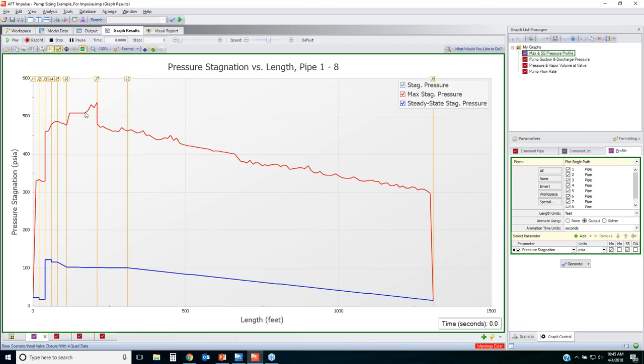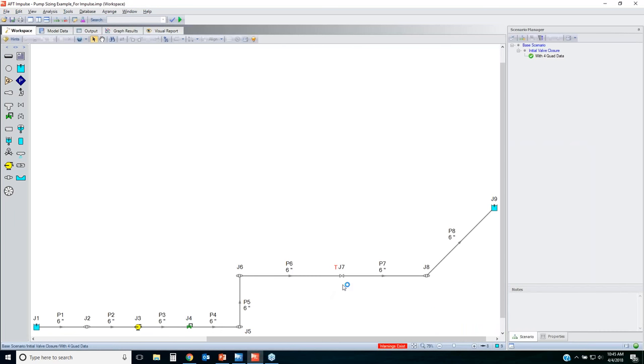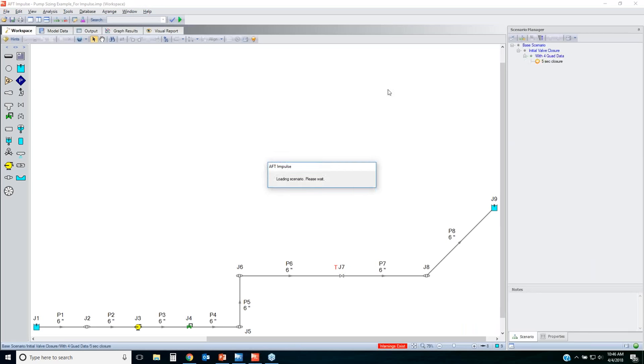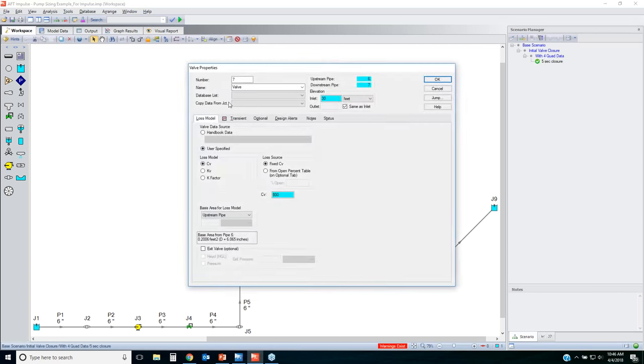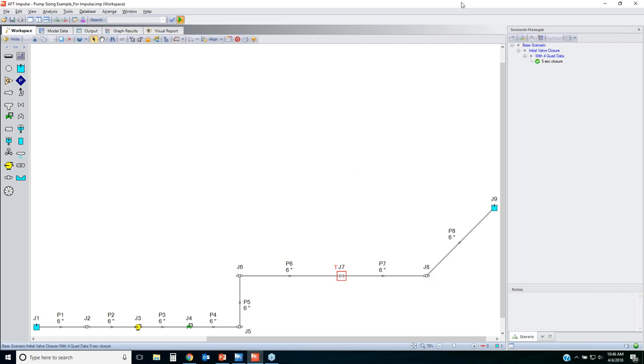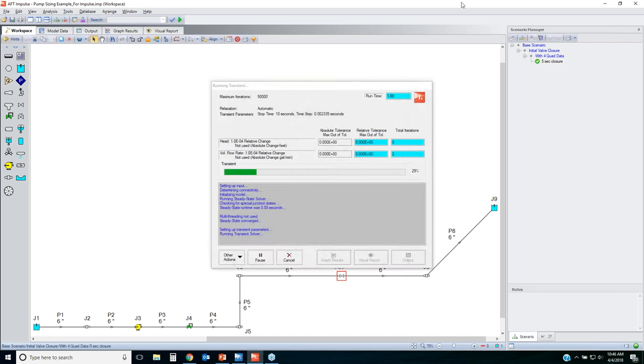Basically, if you're doing a valve closure in one second, that's going to cause large pressure surges. So let's try a five-second closure — I'll create another scenario called 'five second closure' and change the valve to close in five seconds instead of one.